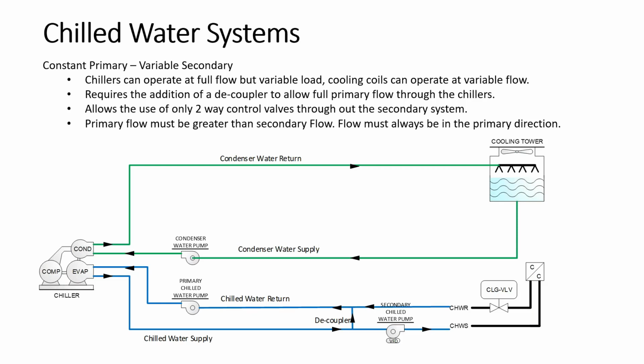The secondary pump picks up water from the supply side and pumps it out to the system in whatever flow is necessary according to how many control valves are open or closed. And so you're able to maintain your flow on the chiller with the primary pump, but it's constant, and vary the flow to the load on the coils to use only as much water as you need. So you're getting some benefit out of that because you're not constantly flowing all that water throughout the entire system like you had with the primary only system, but you still are maintaining a constant flow on the chillers. So you're not saving as much as you possibly could.